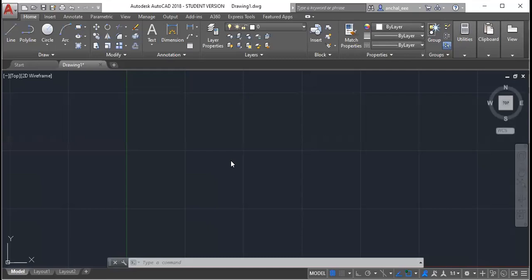Yes, ma'am. Right, second question: draw the sectional plan, elevation and end view of a 5 kVA single phase core type transformer. The circumcircle dia is 80 mm, the limb is square in cross section. Inner dia of LV winding is 83, outer 98, inner HV 114, outer HV 135, wooden pieces in between LV and HV.